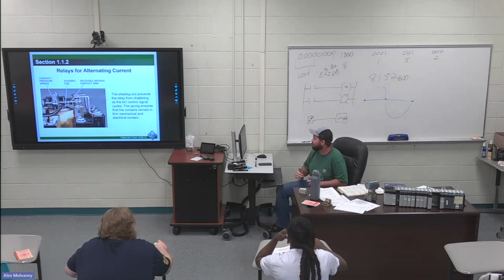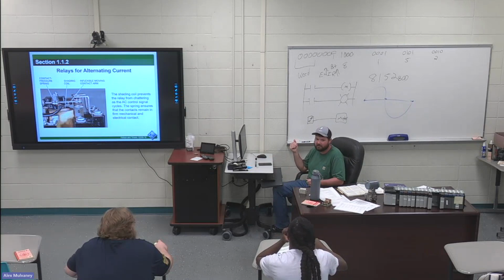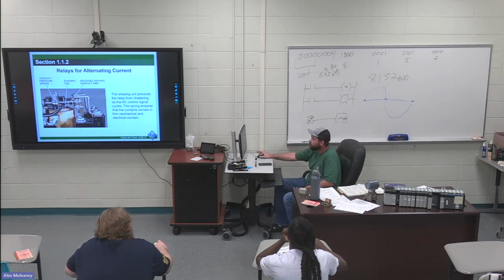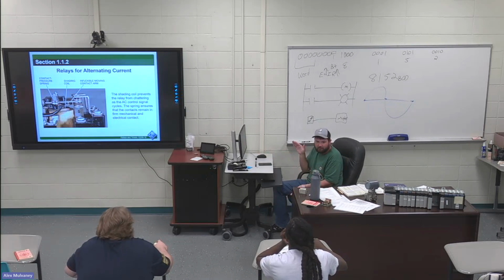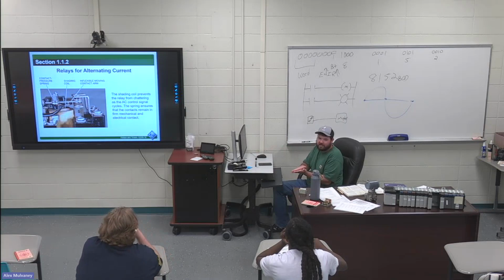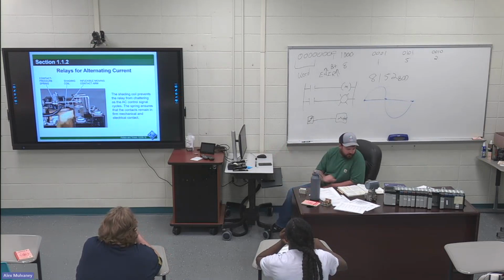If you ever walked into a plant or something like that and you hear a humming noise around some contactors, that's because for very, very brief moments of time, there's 0 volts flowing through this coil because it's AC, and those contacts are not opening up all the way, but they're opening up, they're chattering. That noise is chattering of coils. What a shading coil does is it eliminates that. Shading coil will allow that magnet to act more effectively and keep those contacts tightly together.